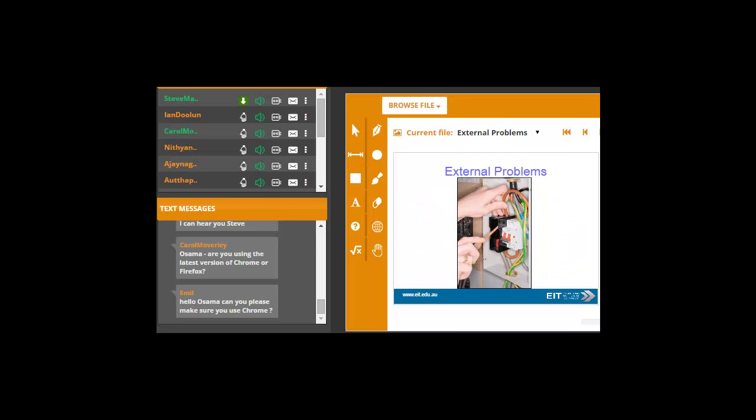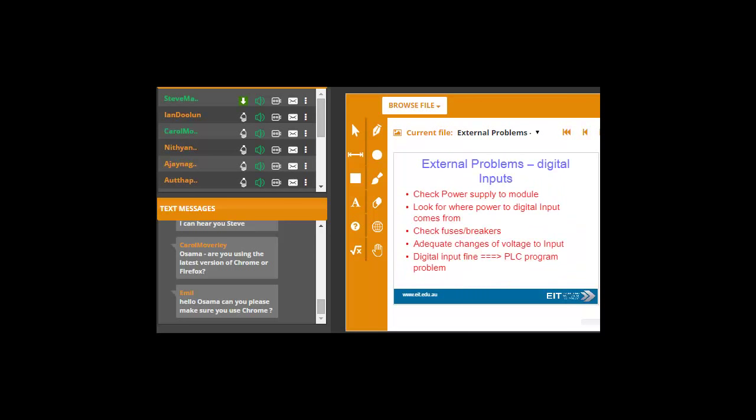If that's not correct, you've got problems. And I'll come back to that point a little bit later when we talk about SCADA systems. Power supply is within the correct range. AC ripple. Batteries on the PLC are OK. Sometimes you've had the nasty problem where the battery's gone, power to the PLC is gone and you've lost your program. So those are some of the typical issues. And obviously, you can examine internal diagnostics to see where there's a potential problem with PLC. So external problems, which I really want to talk about. And there's some subtle external problems, actually, which are really, very strange. And I'll talk about those. Obviously, first thing with external problems, check the power supply to the module.